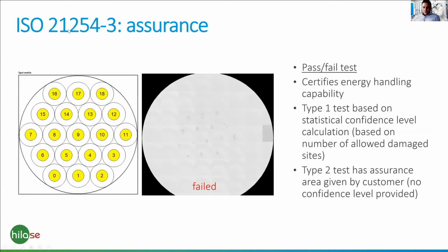Now, ISO 21254-3 is talking about assurance. In this procedure, we are not looking for the damage threshold itself. Rather, we are defining a kind of pass-fail test where we are certifying a specific element for energy handling or power handling capability. There are two types of tests.